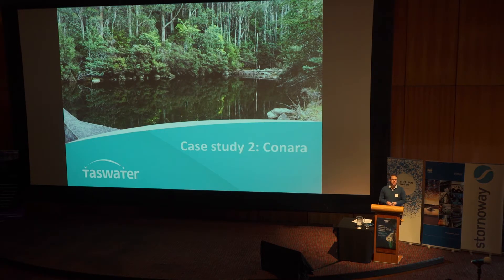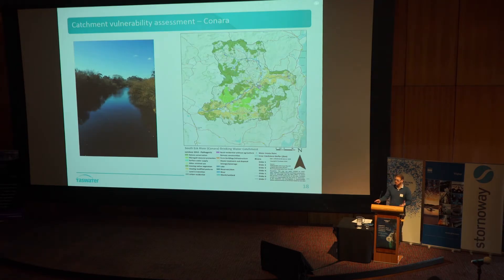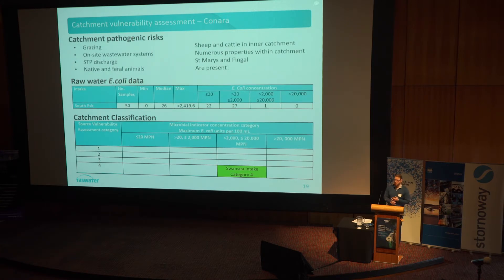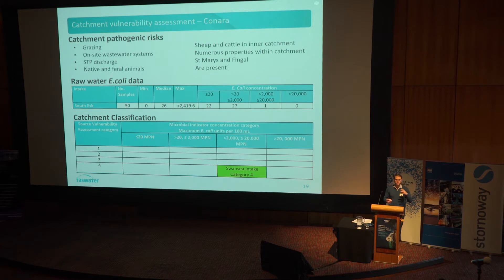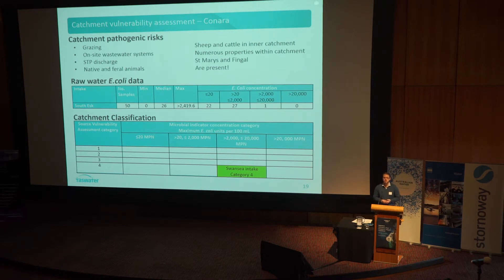Case study two was Conara. This was a bit different — we actually did our catchment risk assessment prior to building our new water treatment plant, so we had that information before the design. Again, we did all the mapping of land uses and went on-site to validate. We were again in a situation with sheep and cattle in the inner catchment, numerous properties probably with on-site wastewater systems, and STP discharges from Fingal and St. Mary's — which put us in a category four catchment. Our E. coli data, though we had less of it, still had the highest concentration in the 2,000 to 20,000 range, confirming we were in category four.